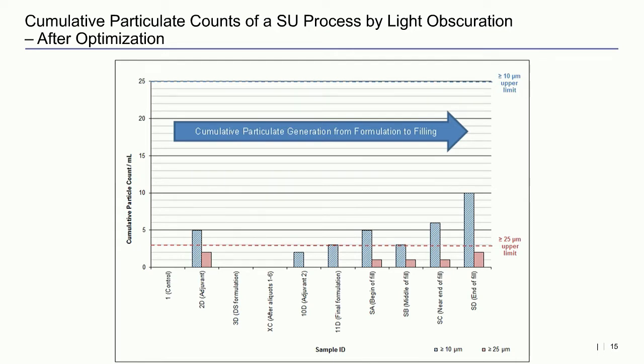And that can be explained by the fact that the peristaltic pump used to fill the product wears the platinum-cured silicone tubing ever so slightly over time. This was expected, and considering the process was run under worst-case conditions, the accumulated count of particles at the end of the process was still well within the acceptance criteria.